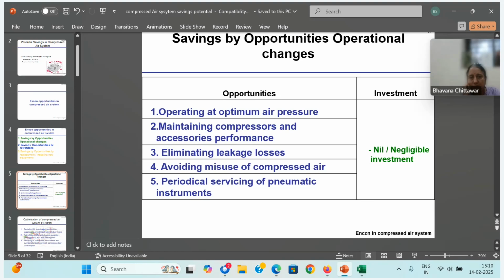Then eliminating leakage losses. No auditor will miss out leakage losses, because the main losses in air compressors are leakage. So you have to periodically check leakage losses. I have been working with certain automobile industries. We used to check shift-wise, when we were paid on the overall leakage reduction. A base level was established before signing the order. Then every week during lunch hours or dinner hours, we would check for leaks, and how much compressor capacity is thrown out for air leaks.